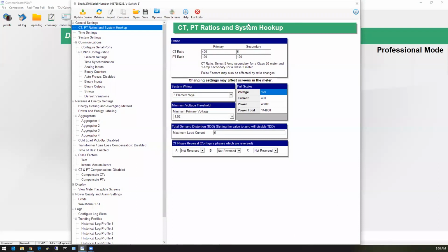So you will receive a pop-up with all your current meter settings. There are many options. Don't be intimidated. This is a basic programming. Your meter will function properly by our simple setup of simply putting in your correct CT ratios and PT ratios, 1-to-1 for Y connected. If you have a delta connected system or 2.5 element Y, you may select that option.